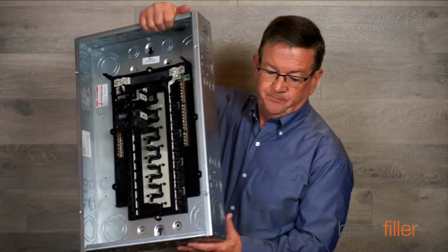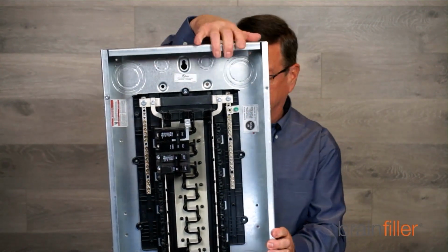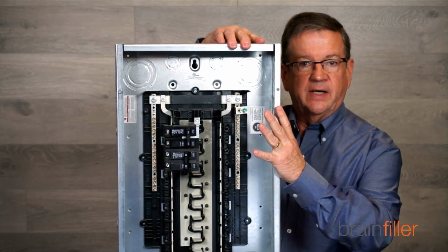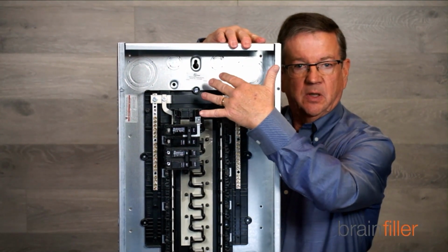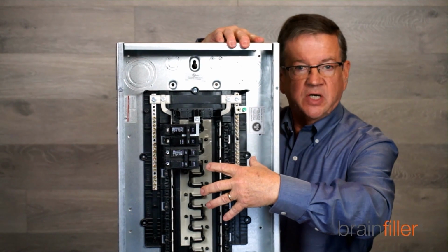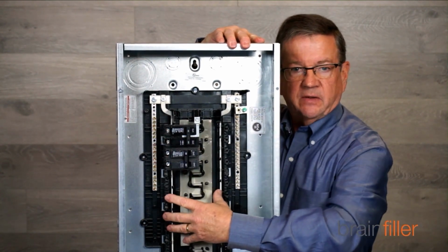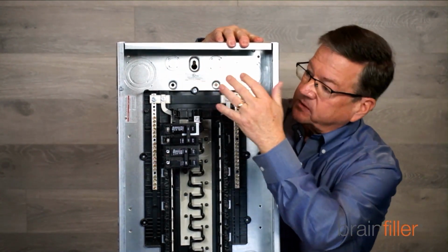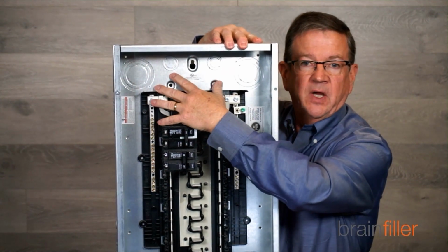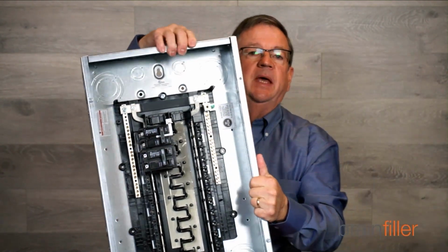I believe what you're talking about, I can illustrate that here. I believe the question is, if you try to create an electrically safe work condition, you have the main open here. Isn't this still considered energized? Yes. This may be de-energized down here, but you have exposed conductors. I don't have a main in this, but you would have exposed conductors up here. So for many, that would still be considered a shock hazard, electric shock hazard, and also an arc flash hazard, unless you isolate it with a device upstream.